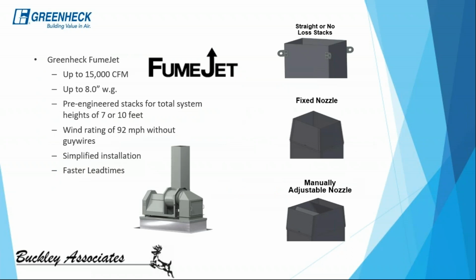So the Vector fan line is definitely the most optimal solution. That is the best solution for any isolation room application. However, if certain constraints, say roof space or budgetary limitations, or even time, don't allow for the full installation of a Vector fan, Greenheck also offers this Fumejet line. So it's not as robust as the Vector line, but we've seen it function as a viable alternative to those Vector fans.